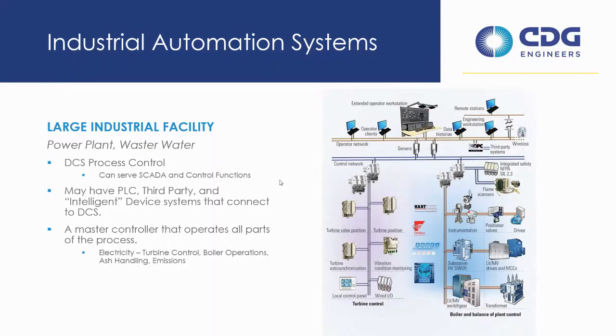So you can have a PLC system that just runs maybe the ash handling or a standalone process that you don't really need. That's not really critical to the power plant operations, but you can take in that information to the DCS and communicate it to your operator folks. It's a master controller. It'll operate all parts of the process, like I said before. So it'll operate all the turbine control, the boiler operations, ash handling, emissions, that sort of thing.